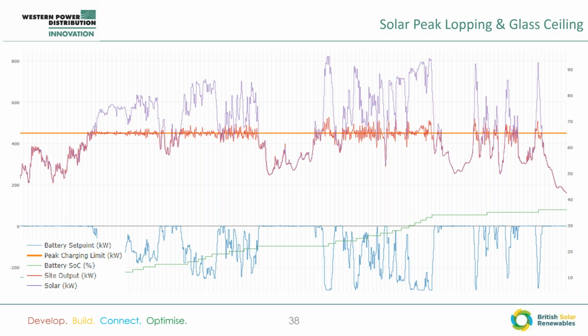There are some excursions both above and below the line. Some of these are not the fault of the battery. So if you're looking towards the right-hand side of the day there, actually the generation was more than 310 kilowatts above the peak lopping limit we'd set. So the battery ran out of power capacity to be able to absorb that.